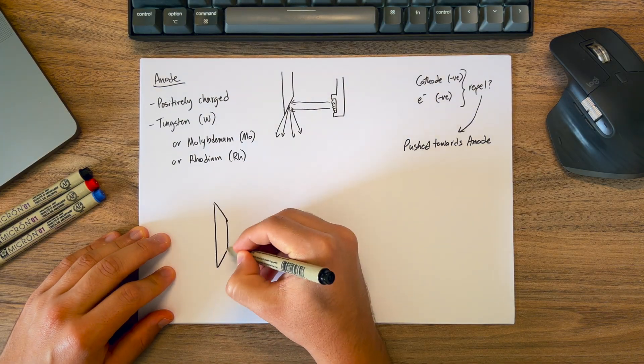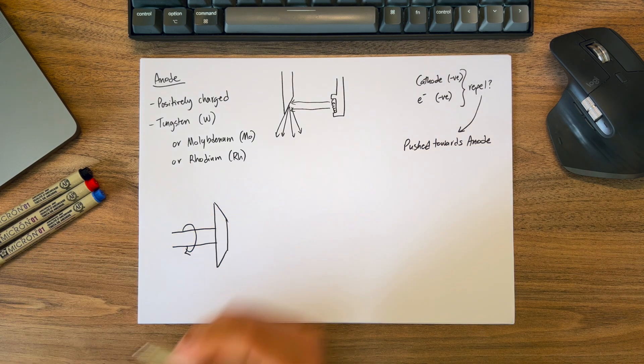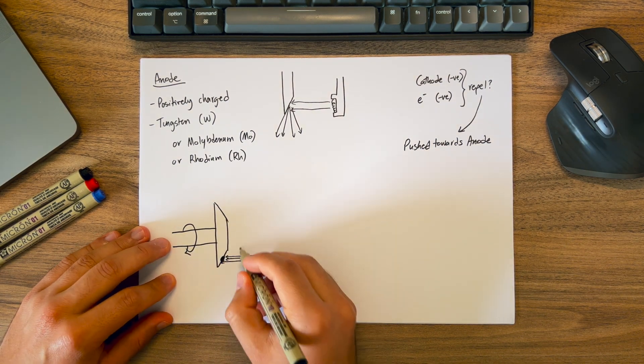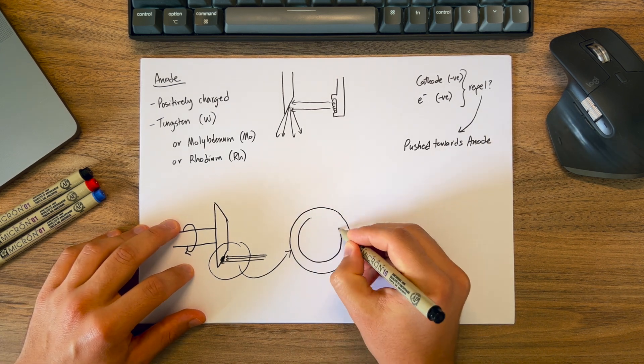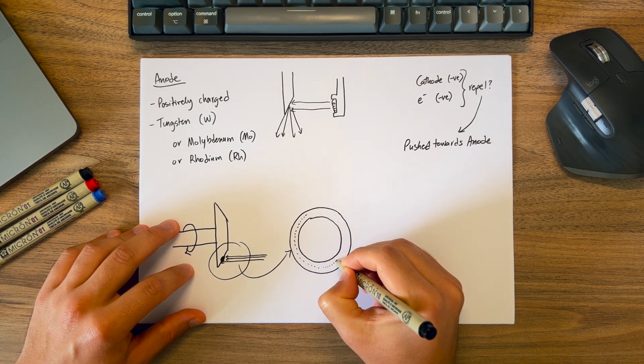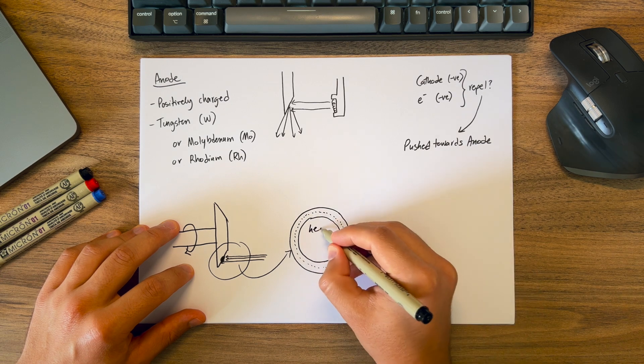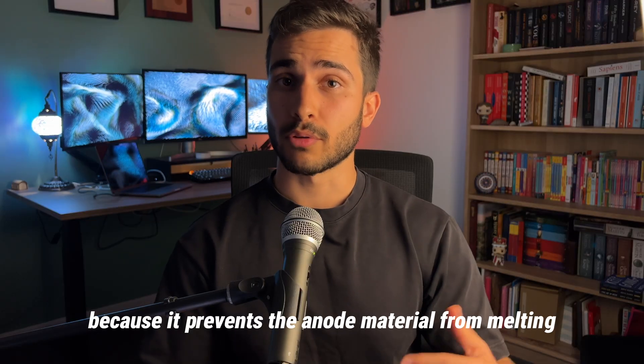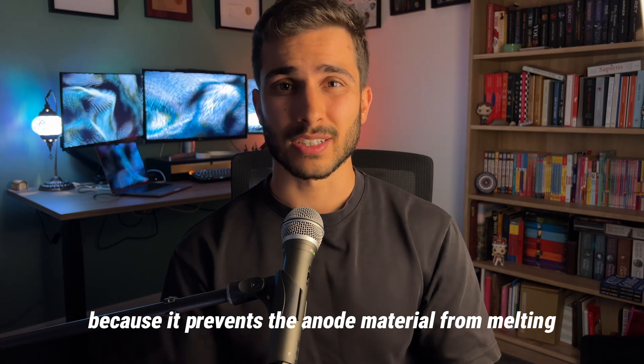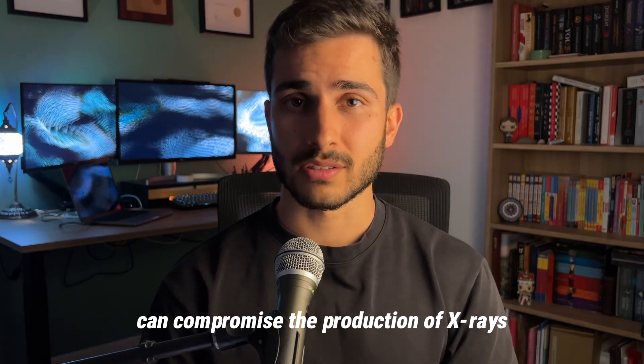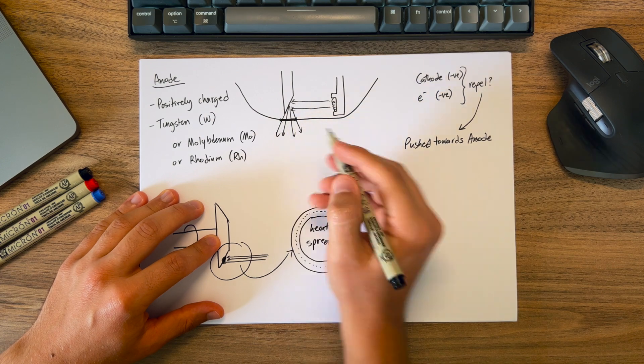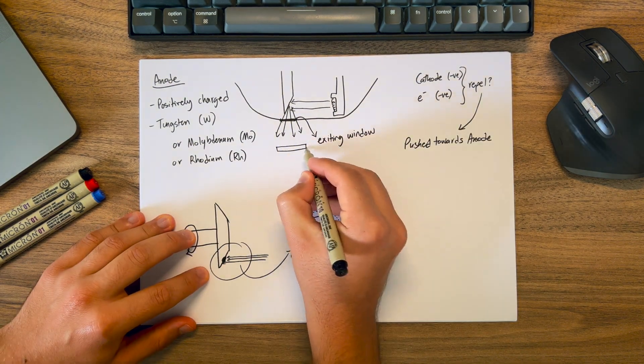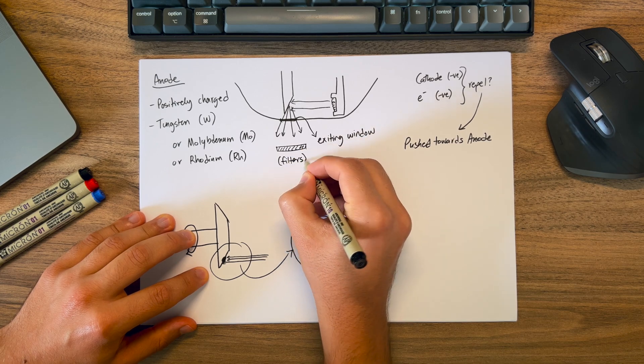The anode is actually on a rotor, meaning that it rotates. It's like this because when the electron collides with the anode, it also generates a lot of heat. So to counteract that effect, the anode rotates to spread the heat over a large surface area, which prevents it from overheating in one single spot. This is important because it prevents the anode material from melting, which can compromise the production of x-rays. Once the x-rays are produced, they're then guided through what's called an exiting window, which can go through various filters and collimators before it reaches the patient or detector.